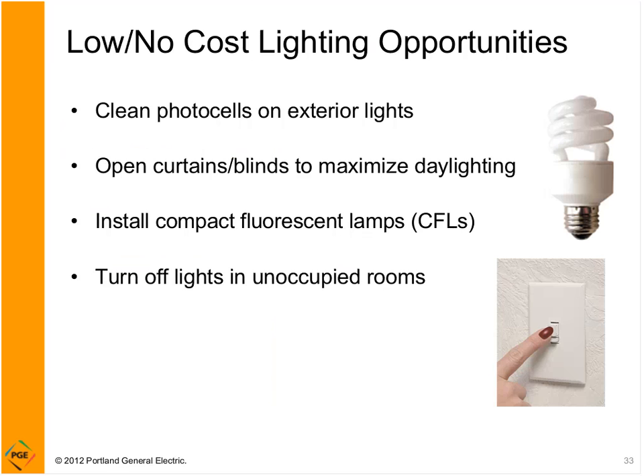We'll cover some low and no-cost lighting opportunities. Something I see quite a bit when I'm out working with customers is lights that are on in the middle of the day. A lot of exterior lighting is controlled by photocells, which is basically just a sensor. When it senses that there isn't very much light, the lights turn on. If the photocells aren't cleaned regularly, there's so much dirt and dust that accumulates on them that the lights stay on all the time, even in the middle of the day. So it's just a matter of cleaning those photocells off on a regular basis. It really limits operating time to dusk till dawn with outdoor lighting.